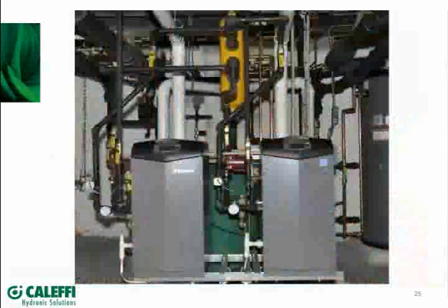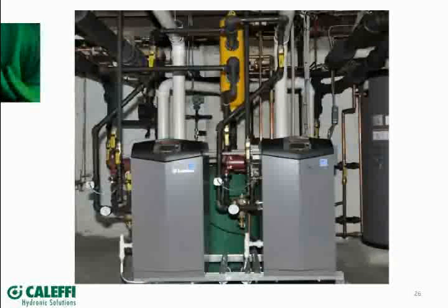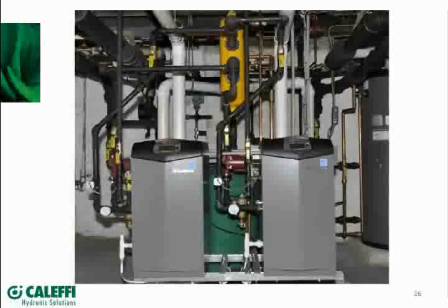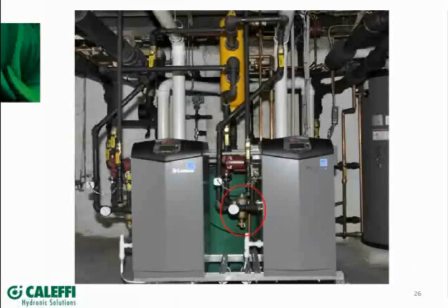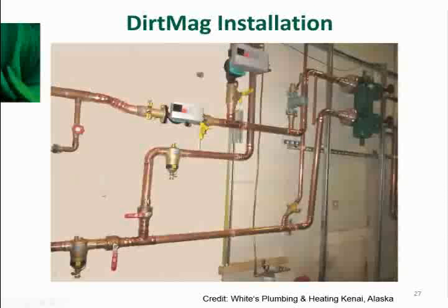Here's a picture showing a balancing valve and Z1 zone valves with Y-strainers protecting both the zone valves and the flow setting device. A little better picture here shows dirt separators used on a couple of boiler installations. Focus on the two Caleffi components at the bottom — those are dirt separators on the return side to the boilers, protecting the heat exchanger and pumps from debris.